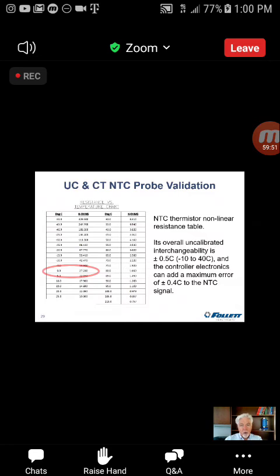All right. However, when you do that, you can't be holding both of them, because if you do, you're part of the circuit. You can only hold one. So make sure you're not part of the circuit. Wrap the wire around one if you can. Hold the other one if you want to, but you can't be contacting both of them. Otherwise, your body is part of the circuit, and it will give you an erroneous resistance reading. So we need to make sure that we're doing that accurately. So that's it. That's the probe validation process.